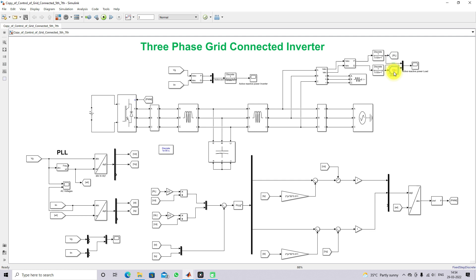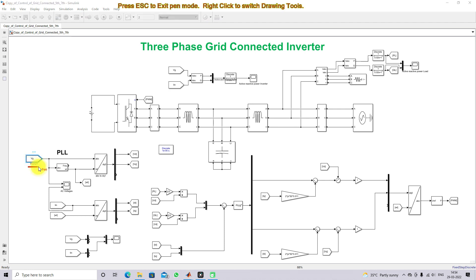We can see the real and reactive power of the load. This inverter is going to be controlled by means of feed-forward decoupling control. To apply that, we use DQ transformation. The grid voltage is measured and processed through a PLL, which generates omega-T — the phase angle with respect to time. The grid voltage is then converted from ABC to DQ using DQ transformation, giving us VD and VQ for the feed-forward compensation concept.